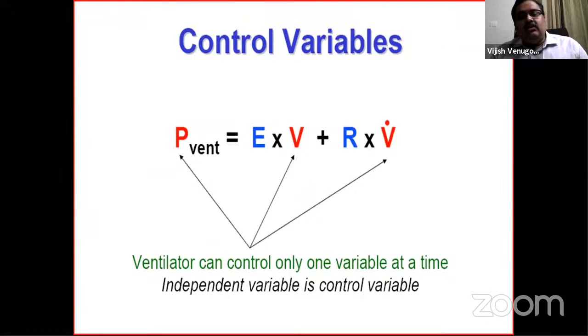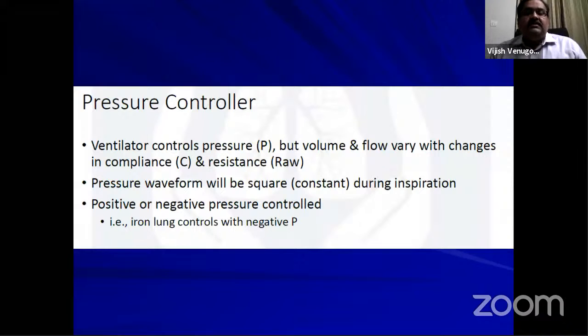So these are the control variables. How many control variables are there? The ventilator can control the pressure, the volume, or the flow. The ventilator can control only one variable at a time. The independent variable is the control variable. So if you are controlling the pressure, both the flow and the volume will be dependent variables. So what is a pressure controller? A ventilator which controls pressure, but volume and flow vary with change in compliance and resistance. Here, if you look at this, the pressure waveform will be square or constant during inspiration.